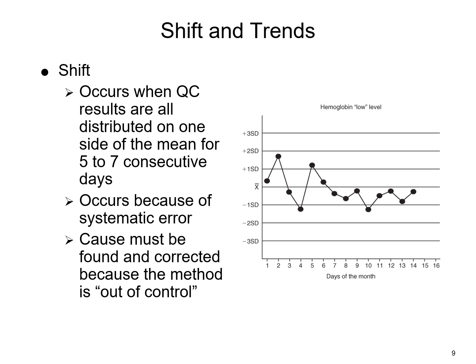Maybe someone didn't reconstitute it right. So this is why it's important that you're always documenting everything that you do. When you open a new vial of QC or reagent, that you document on that vial the date and your initials, so that if you start seeing any kind of trends or shifts or anything go on, then you can kind of start tracking it back.